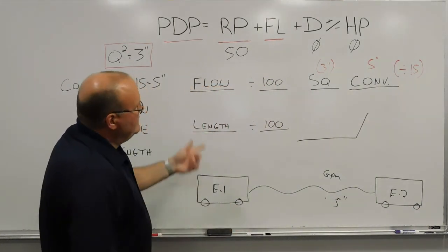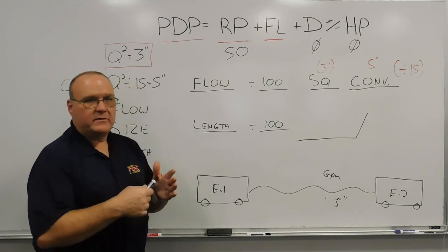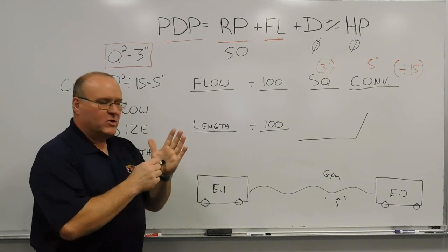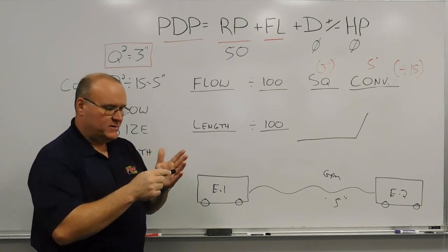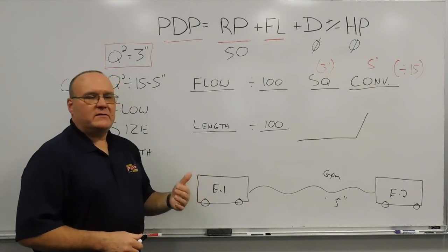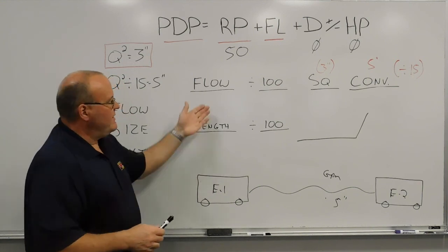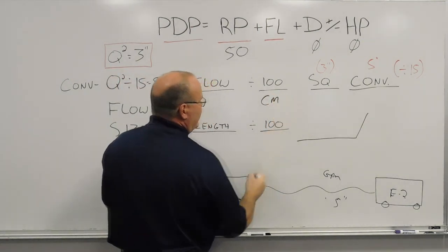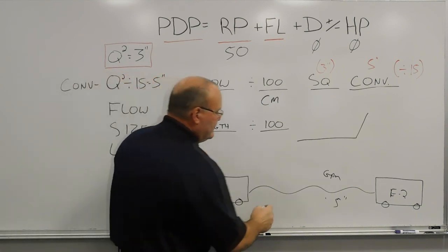So, an in-between number. If I have a whole number, 600, 800, 1,000 gallons a minute, that's an even multiplication. And our hand method is a multiplication sign in the palm. You go to that corresponding finger and square that number. So 8 times 8 or 10 times 10. If I have an in-between number, such as 750 gallons a minute, 850, 950, I come across, and instead of just dividing by 100, we cross multiply. So we'll put a little note right here, we cross multiply, and then we'll say for this example that we're flowing 850 gallons per minute.